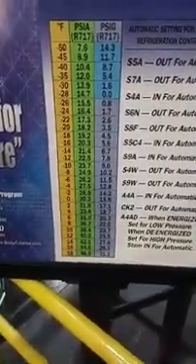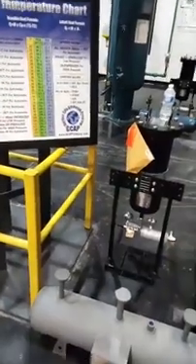Let's say this is our cooler and we're trying to keep that room roughly around 20 degrees. To do that, we need a unique pressure, and we can look at a saturation chart. If I want the room to be 20 degrees — looking at this, this is all the negative side of the chart — coming over to the positive side, roughly about 33 pounds of gauge pressure will do that for us. But that's just a 20-degree medium, and if the room is going to be 20, the ammonia will probably have to be about 10 degrees colder as a rule of thumb. So looking up 10 degrees on the left-hand column, we would need a pressure of roughly 23–24 pounds of ammonia pressure, giving us a saturation temperature of 10 degrees, and the room could be managed around 20 degrees.